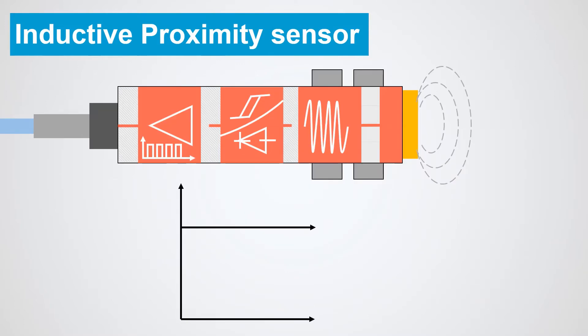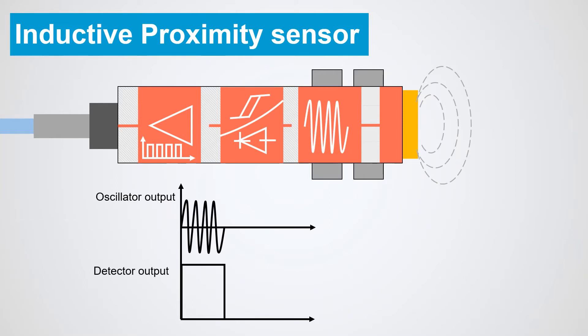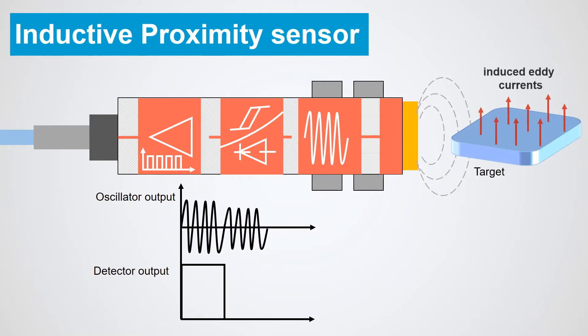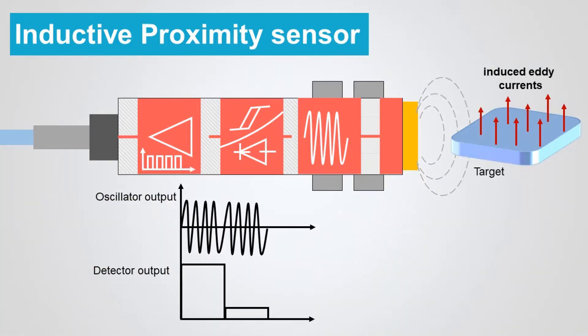The oscillator creates a symmetrical oscillating magnetic field that radiates from the ferrite core and coil array at the sensing face. When a ferrous target enters this magnetic field, small independent electrical currents called eddy currents are induced on the metal's surface. This changes the reluctance and natural frequency of the magnetic circuit, which in turn reduces the oscillation amplitude. As more metal enters the sensing field, the oscillation amplitude shrinks and eventually collapses.